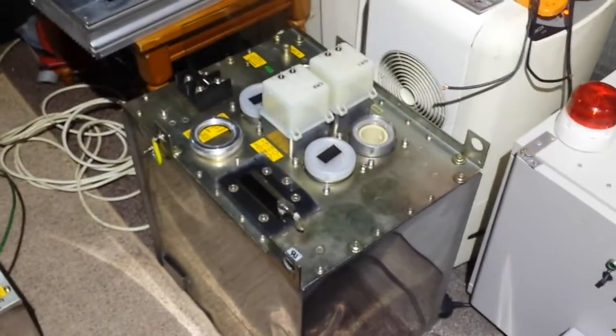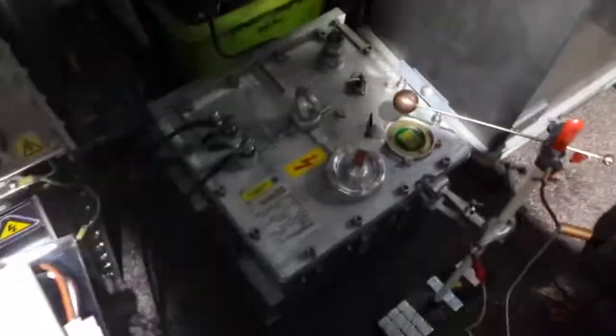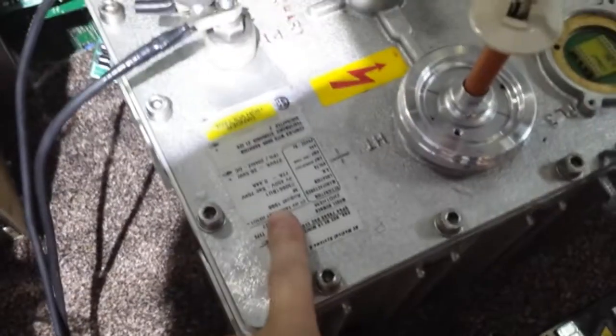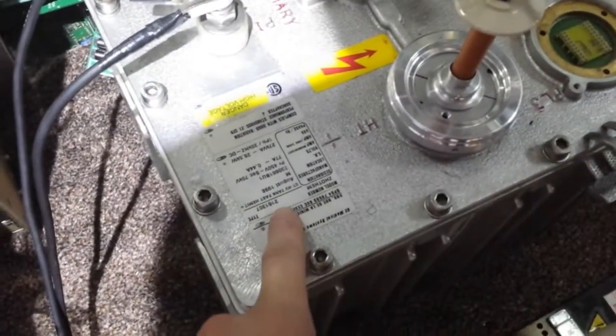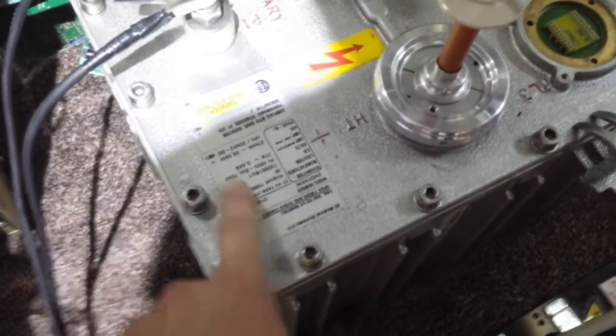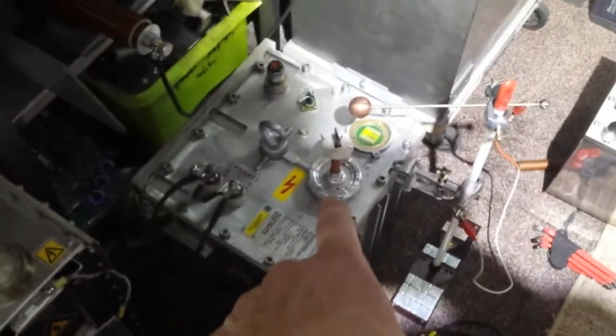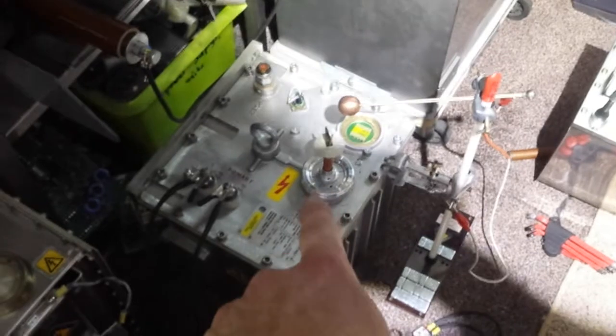150 kV X-ray transformer. 65 kV is it, this one? Trying to think. Oh, 70 kV, sorry. Very high current, because there's 4 X-ray transformers in there in parallel.